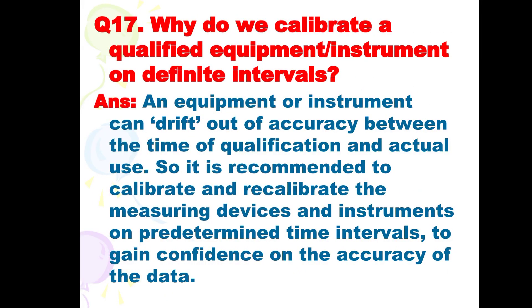Next is: why do we calibrate a qualified equipment or instrument at definite intervals? The answer is: an equipment or instrument can drift out of accuracy between the time of qualification and actual use. So, it is recommended to calibrate and recalibrate the measuring devices and instruments on predetermined time intervals to gain confidence in the accuracy of the data.